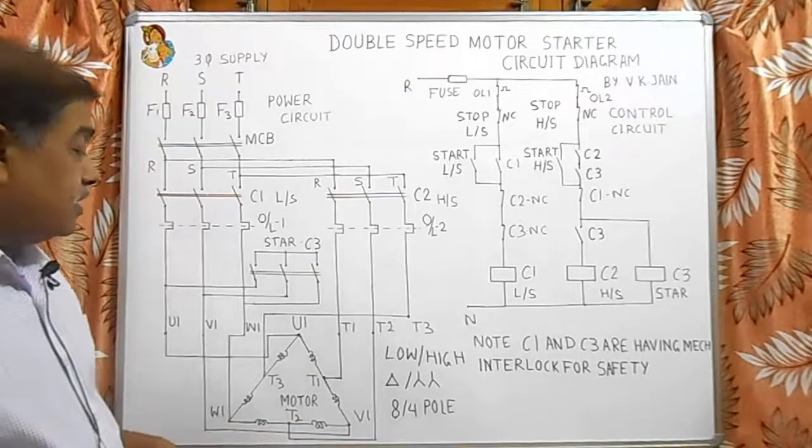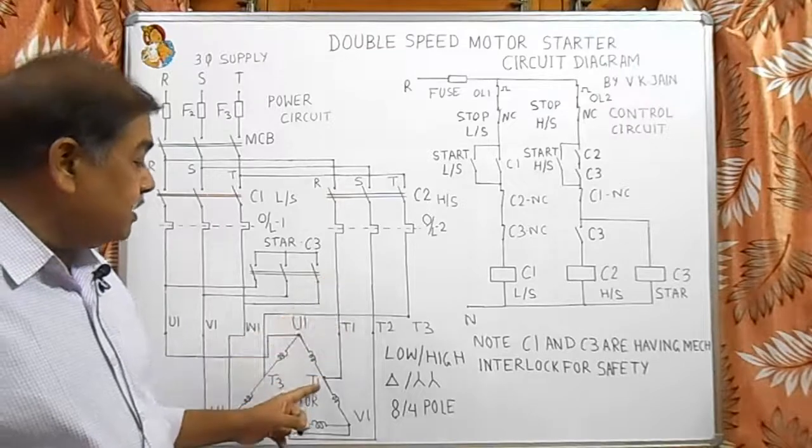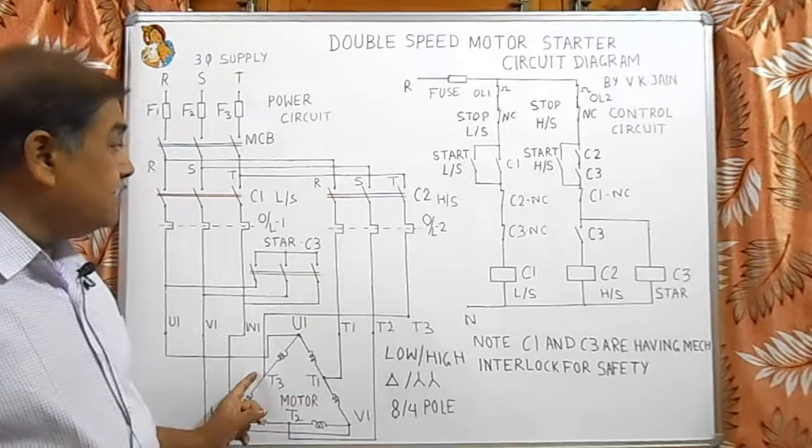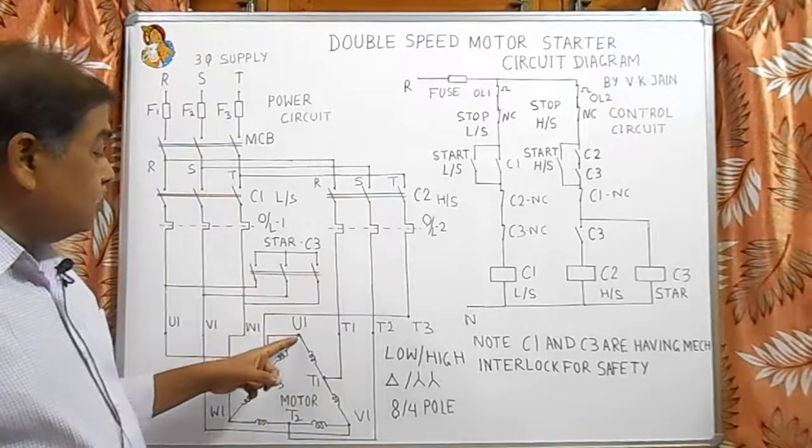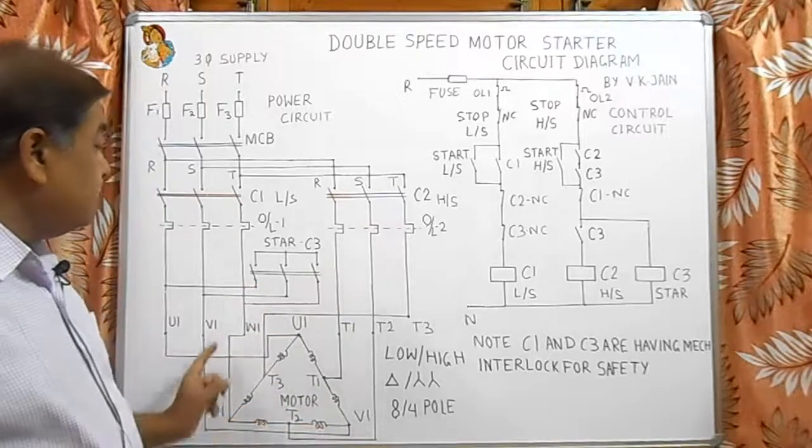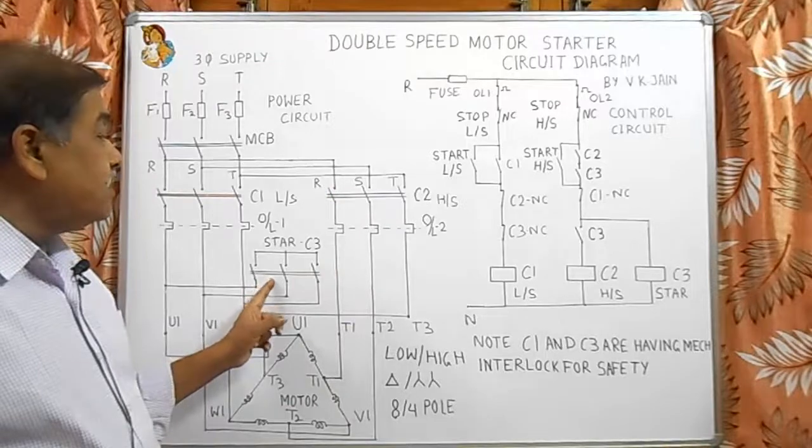For running at high speed we have to give supply to the terminal number T1, T2 and T3 with the help of C2 contactor, and U1, V1 and W1 are short circuited with the help of C3 contactor.